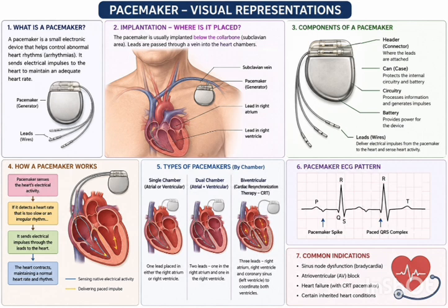So the pacemaker contains important components. First, the battery. It provides the electrical power to the pacemaker. Usually it is made of lithium iodine. Battery life comes under 8 to 15 years. Next, the second one is the pulse generator. From the battery, the electrical impulse is generated.